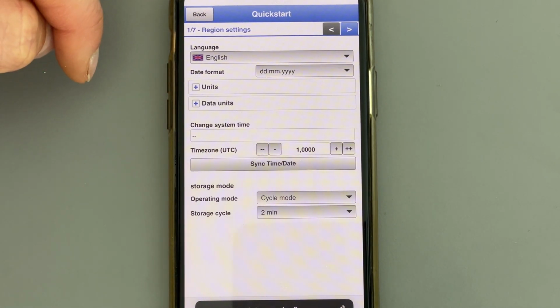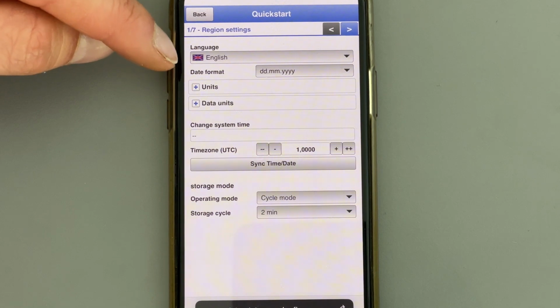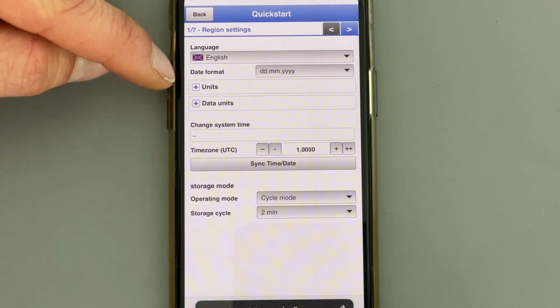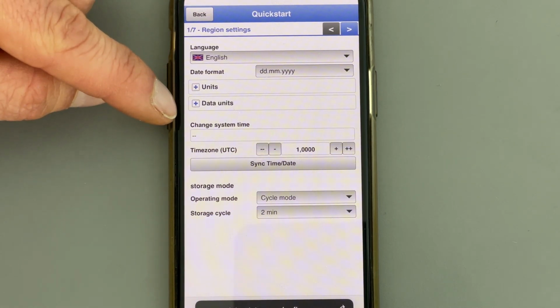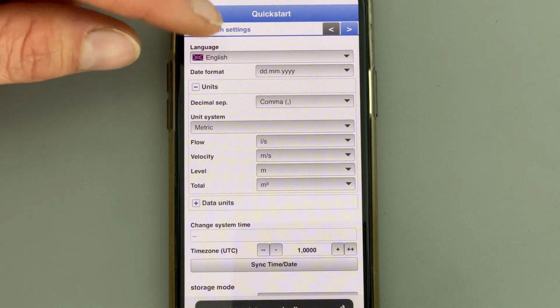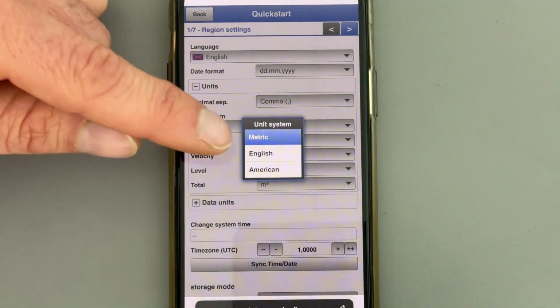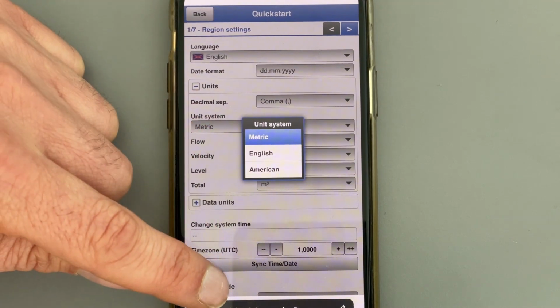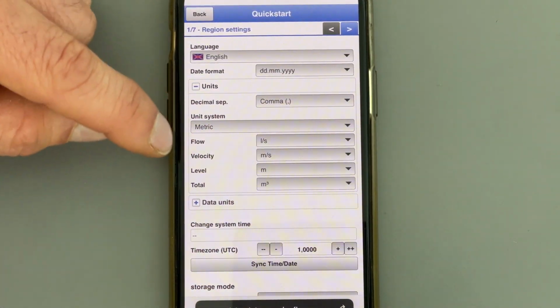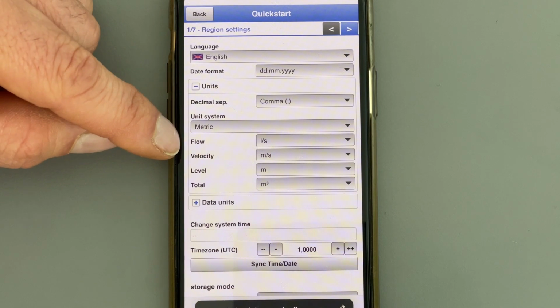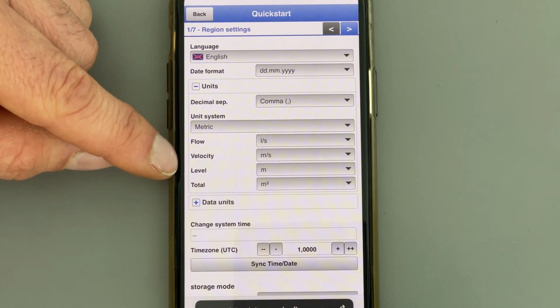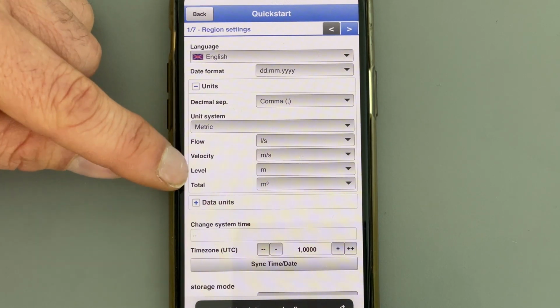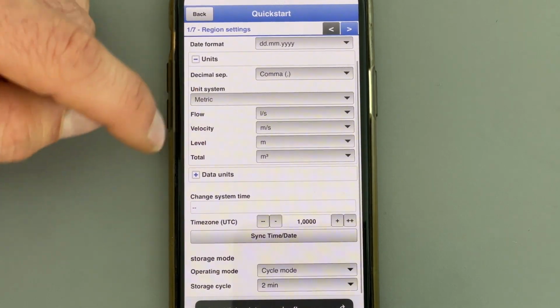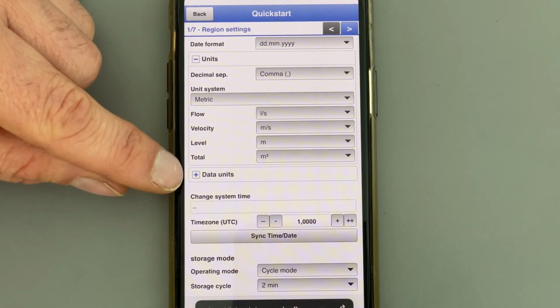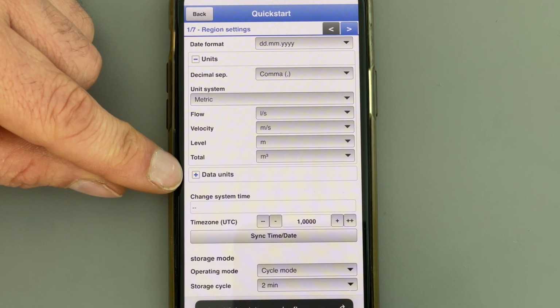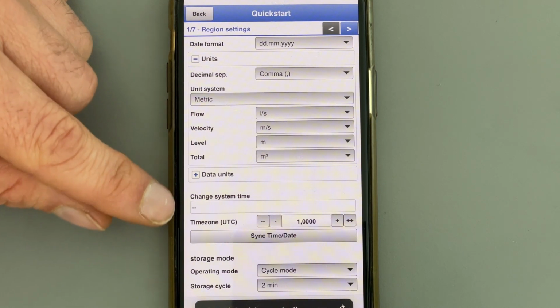On the first page, you get the region settings, like the language, the date format, and the units which should be used. You can choose here, for example, between metric, English, or American units. Here metric is in liters per second for the flow, velocity in meters per second, level in meters, and the totalizer in cubic meters. The same applies for the data which should be saved on the device.